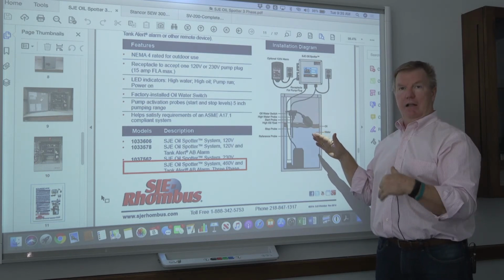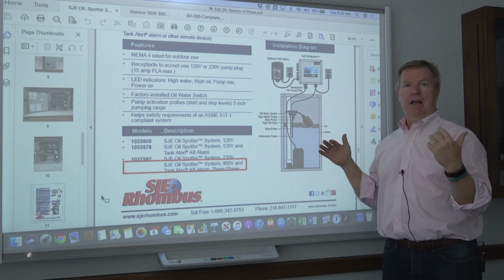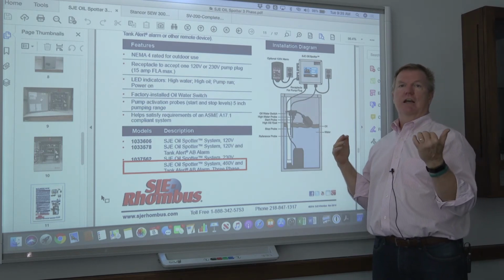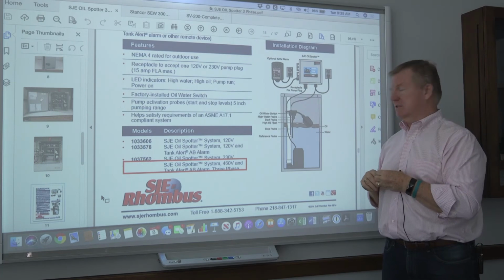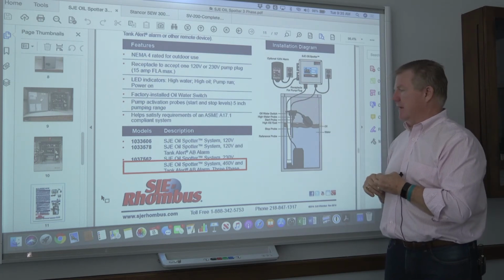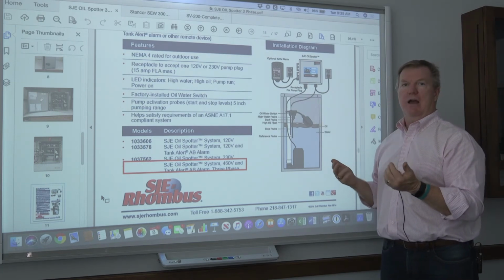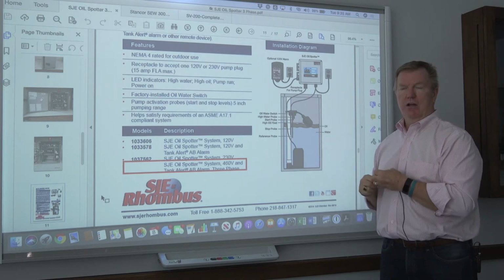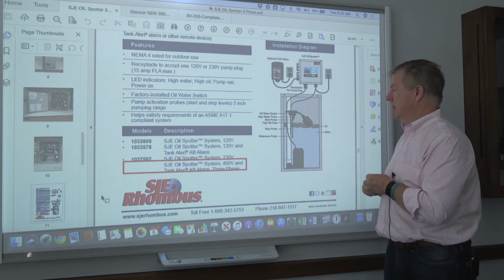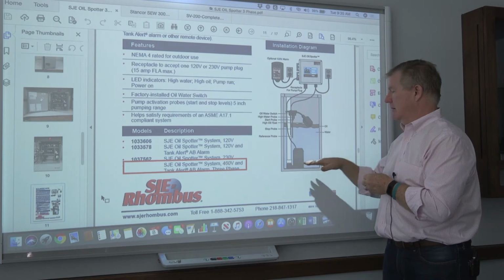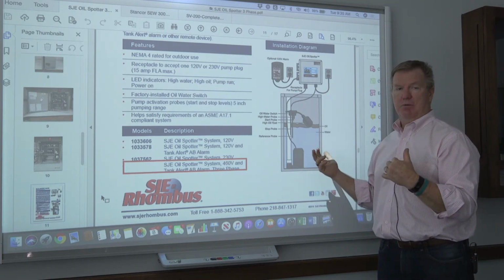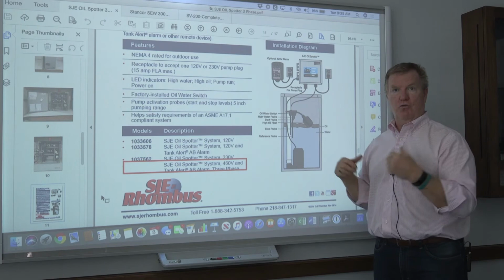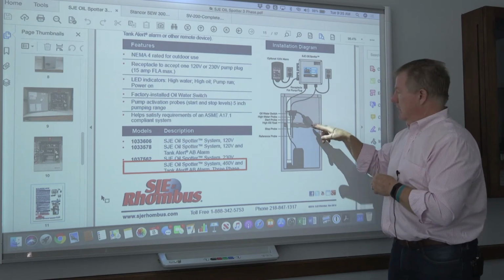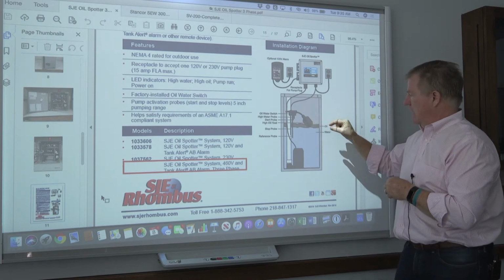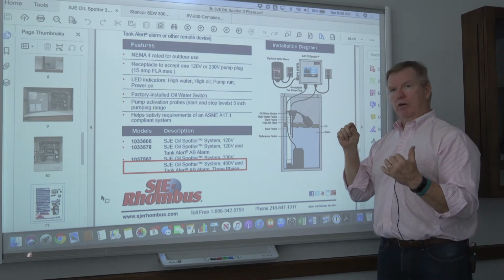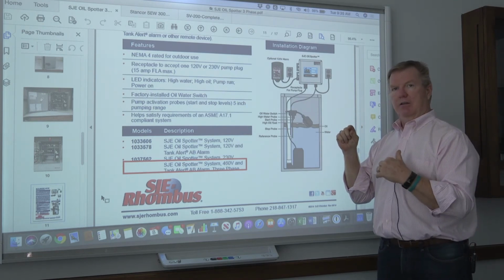There's equipment in an elevator shaft that has oil in it that could potentially leak into the sump. That's why the code requires that you have an oil minder style of sump pump in a pit that prevents the sump pump from pumping oil into the storm drain or into the sewer.